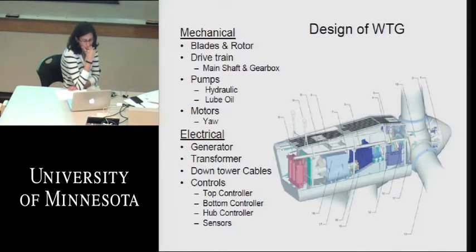There are other configurations. You can have the transformer at the bottom of the tower, which means you've got to bring all of that current, 1,500 amps, down in multiple cables per phase, instead of using one cable that has all 3 phases in it. So it's a design choice the manufacturers make, putting the transformer in the nacelle or putting it down at the bottom of the tower.